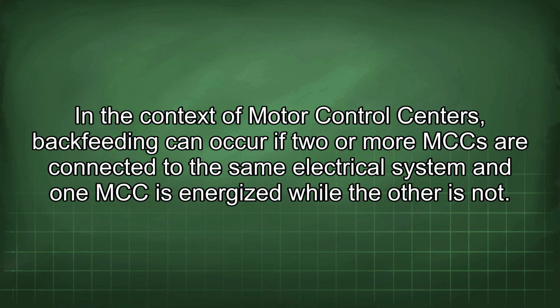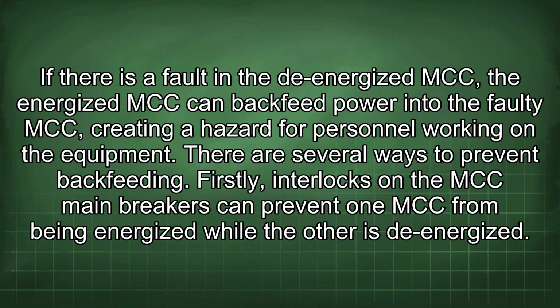In the context of motor control centers, backfeeding can occur if two or more MCCs are connected to the same electrical system and one MCC is energized while the other is not. If there is a fault in the de-energized MCC, the energized MCC can backfeed power into the faulty MCC, creating a hazard for personnel working on the equipment.